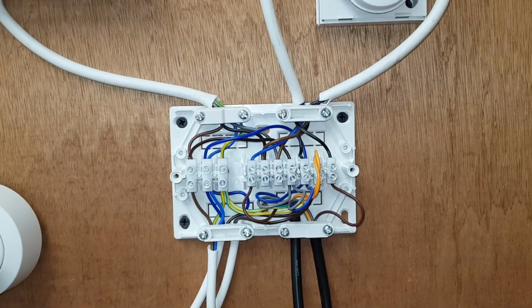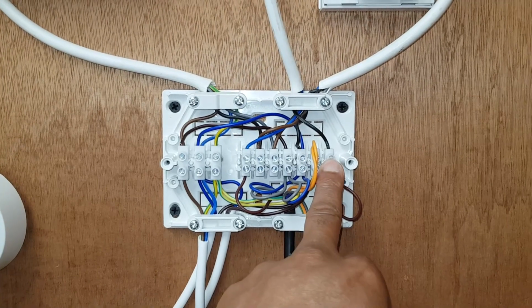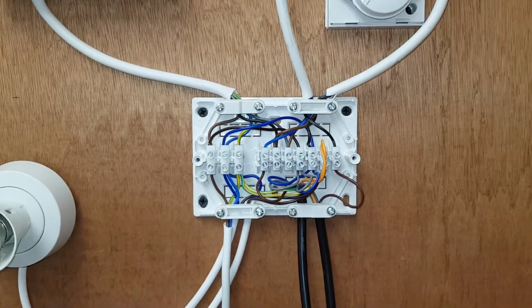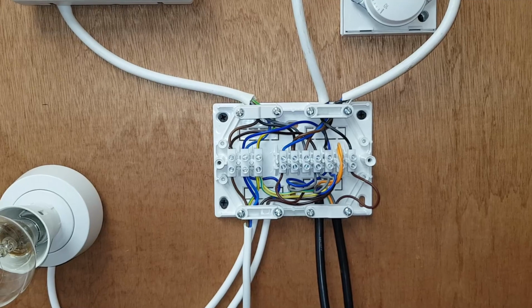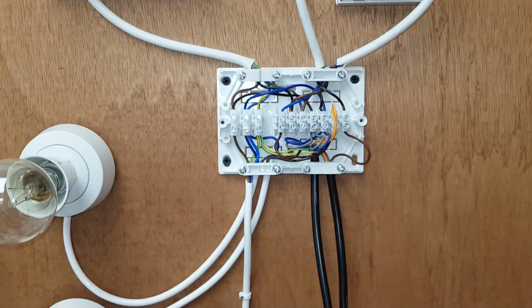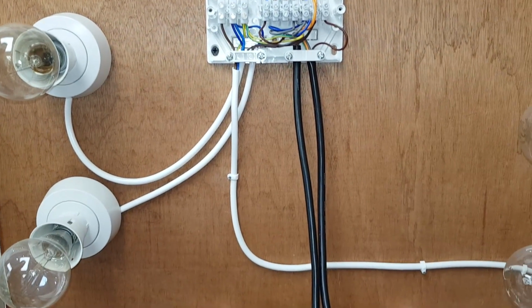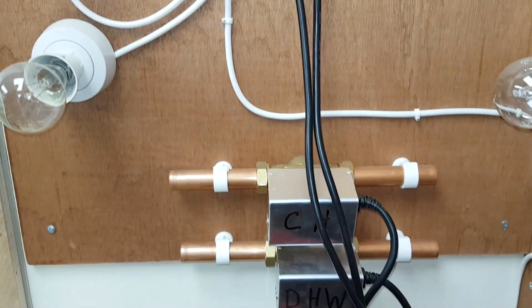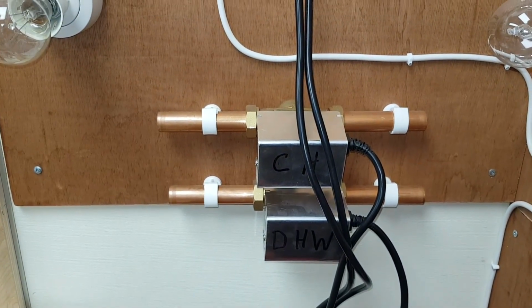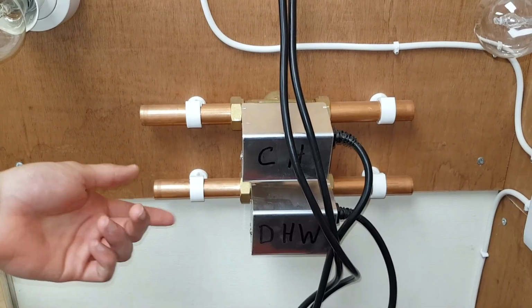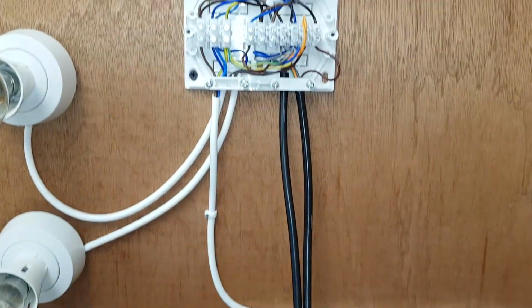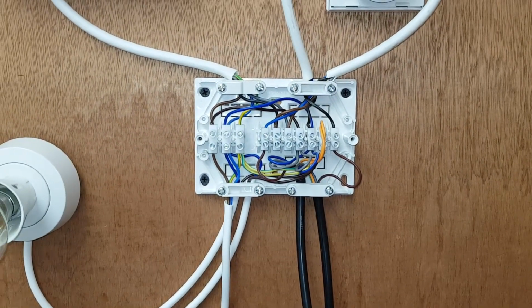Now, another fault. We've got power here, but the heating, so the hot water's not come on. So what do you think that would be? So that could mean that the motor in the zone valve hasn't been activated, or the switch has been made, but it hasn't sent any power to start the pump and boiler. That's it. Excellent. Well done.